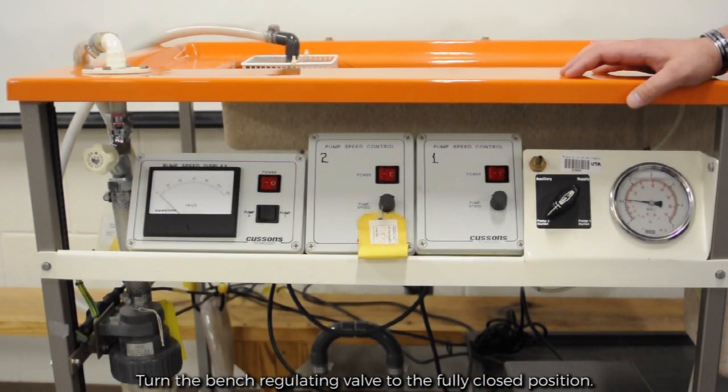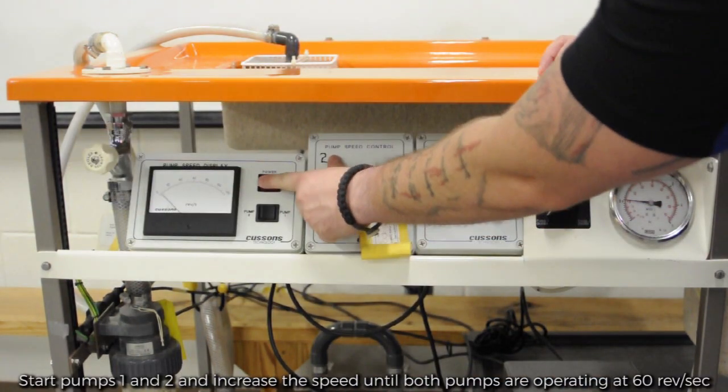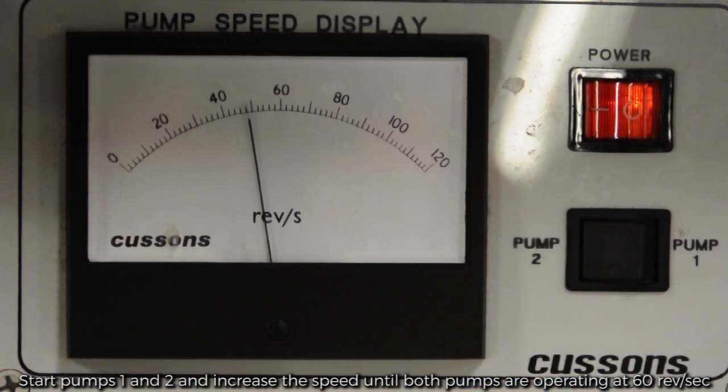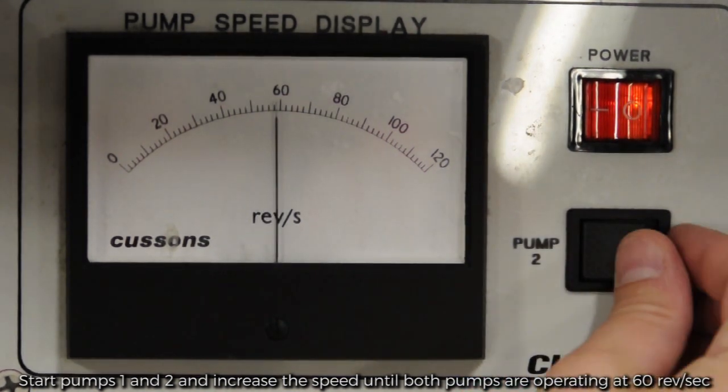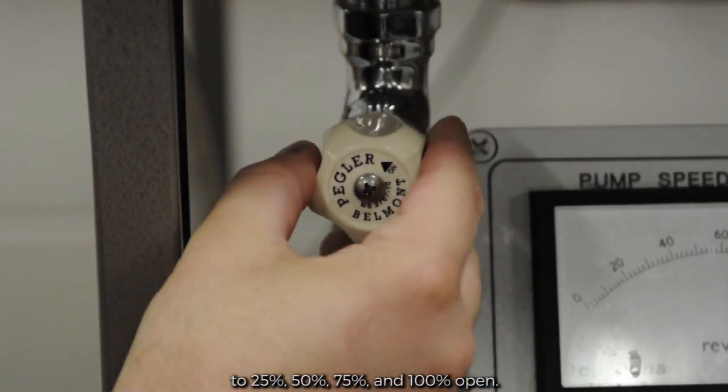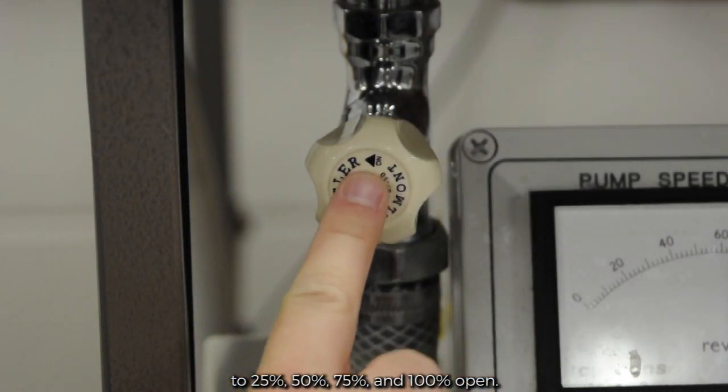Turn the bench regulating valve to the fully closed position. Start pumps one and two and increase the speed until both pumps are operating at 60 revolutions per second. Repeat the previous step by regulating bench outlet valves set to 25%, 50%, 75%, and 100% open.